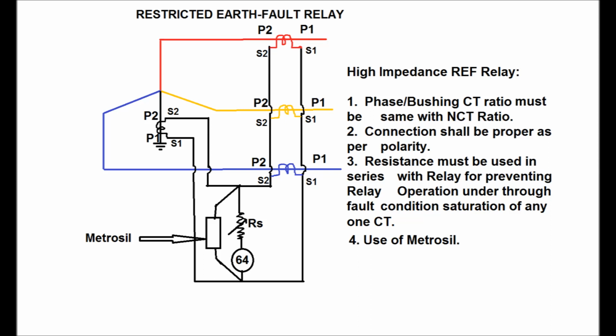Number 4 is the use of metrosil, that is to limit the peak voltage developed during fault condition. Metrosil must be used if the peak voltage is greater than 3 kV. So these are the criteria required for high impedance REF relay.